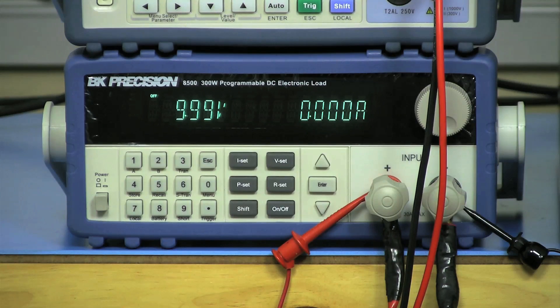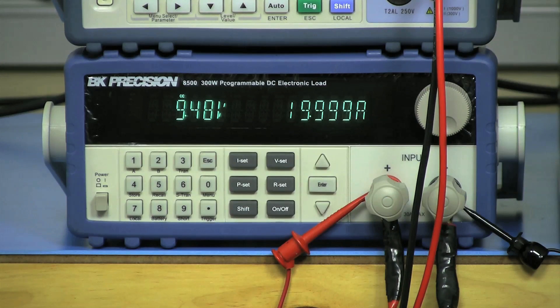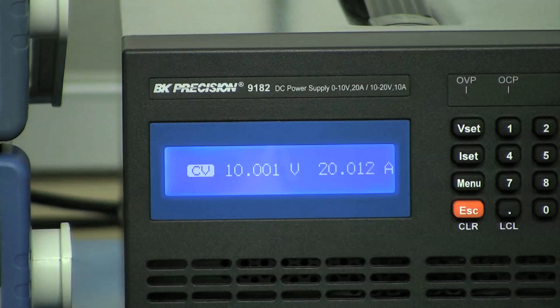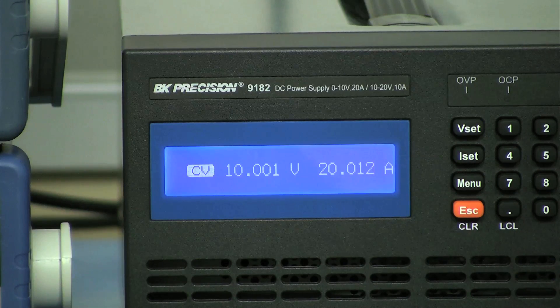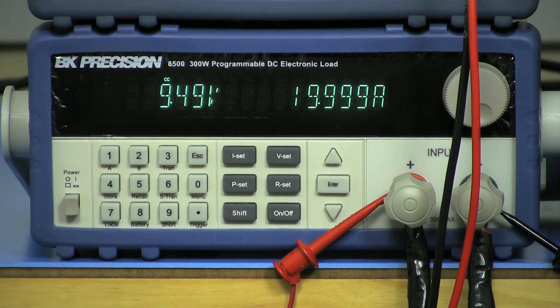Now as soon as I press the input on-off button on the 8500, it will draw 20 amps from the power supply. Observe the power supply to verify that 20 amp is coming out. And also do the same on the load's display.